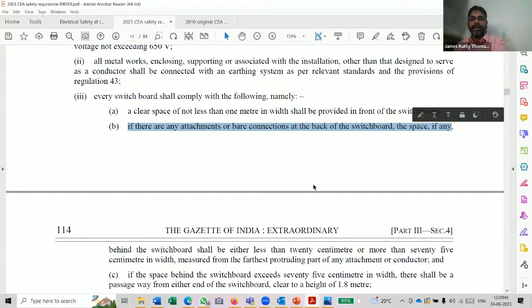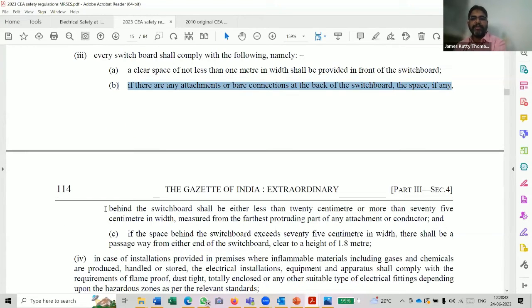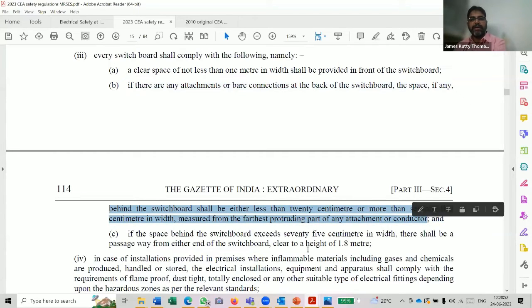I think it is okay that 20 centimeter, I think somewhere it is there, 20 centimeter. If it is completely sealed and if the clearance is below 20 centimeter, I think no issue. Otherwise, it should be more than 75 centimeter. I think it is okay because for maintenance, that panel should be shifted from there for maintenance. Otherwise, 75 centimeter is okay. I think it is okay.